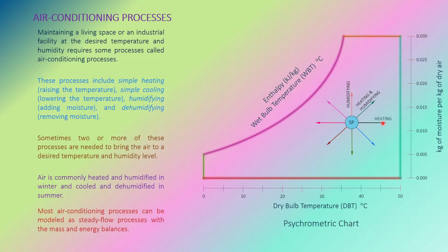Relative humidity is defined as moisture content over moisture capacity. When the moisture content remains constant, whereas the capacity increases because you are heating it, it's just like the space in between air particles. The air particles tend to move further away from each other, but the content remains constant, so the relative humidity will drop during the heating process.